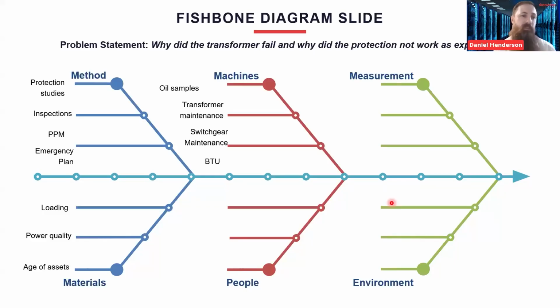Not on this particular circuit, but where they have identified some slight levels of PD, on one in the past where it had been highlighted, there was a clear escalation plan. It was identified and documented based on the risk, and a remedial plan put in place where we isolated, interrogated, and then identified a slightly loose connection, which was rectified. So I wouldn't say a definite set-in-stone plan, but a process that had been put in place as part of our due diligence and in line with our loss prevention and risk management processes.